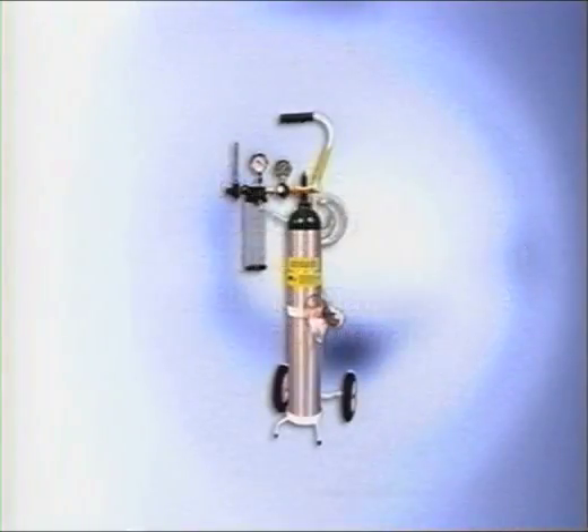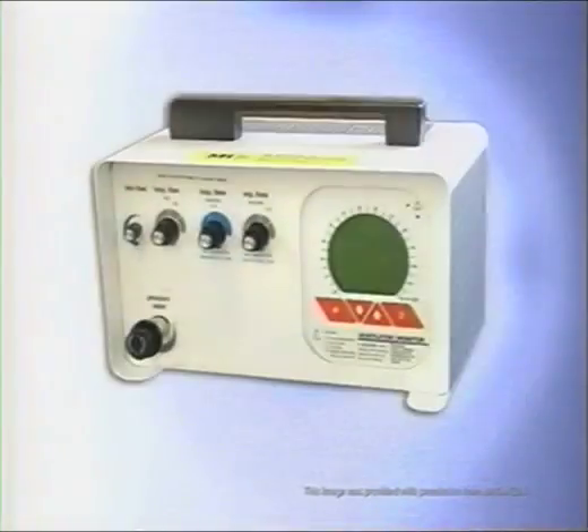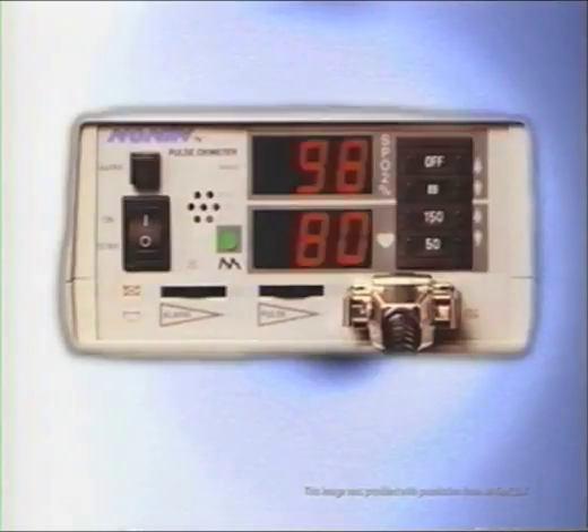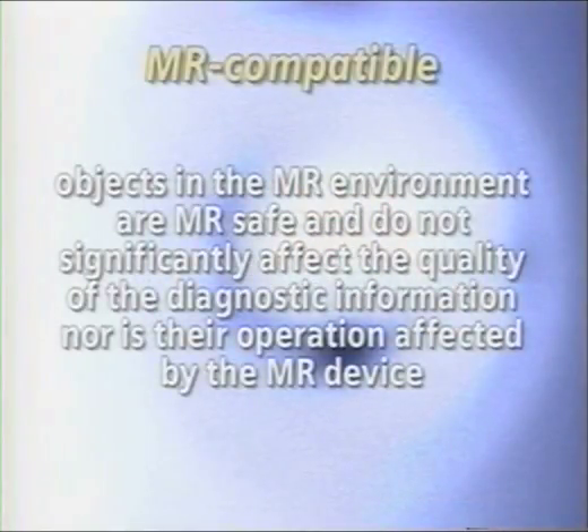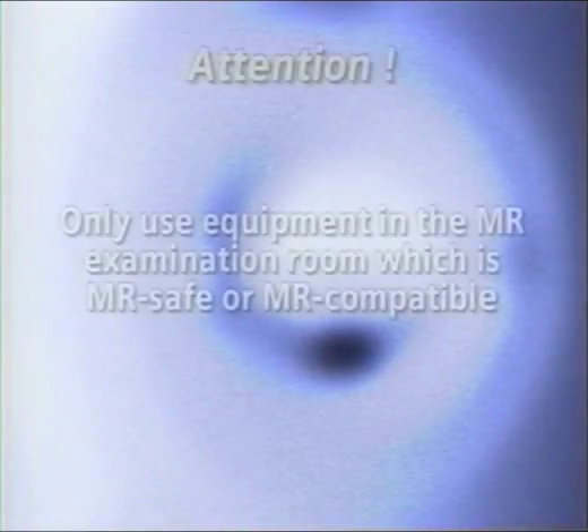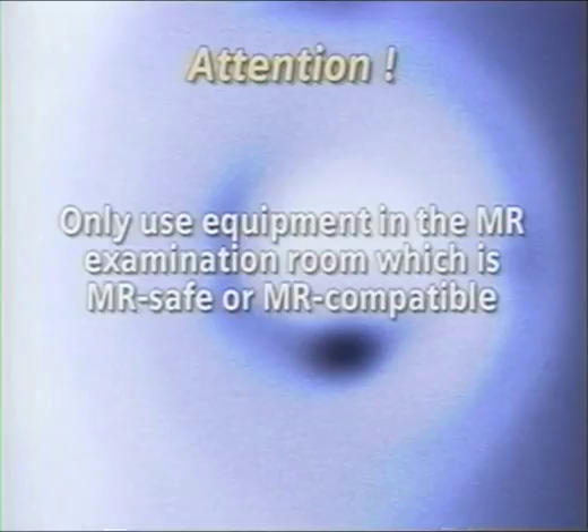These objects are MR safe. This means objects in the MR environment which present no additional risk to the patient or other people, but may affect the quality of the diagnostic information. These objects are MR compatible. This means they are MR safe in the MR environment and do not significantly affect the quality of the diagnostic information, nor is their operation affected by the MR device. They are specially labeled and can be used without consideration. Attention! Only use equipment in the MR examination room which is MR safe or MR compatible.